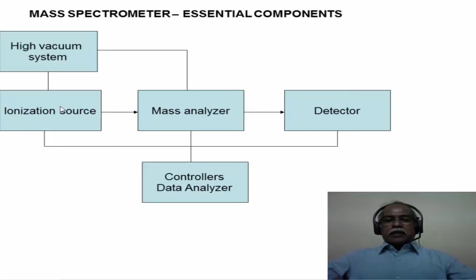Electrospray ionization mass spectrometry as an ionization source and a quadrupolar mass analyzer is a very powerful combination in mass spectrometry. Many modern spectrometers are equipped with this combination as a standard tool for mass spectrometry. Generally, in mass spectrometry we have a very high vacuum system, and the ionization source is also under high vacuum, of the order of 10 to the power minus 6 or minus 7 torr. But there is an exception in the case of electrospray ionization mass spectrometry and matrix assisted laser desorption ionization mass spectrometry, where the ionization can take place at atmospheric conditions, and then the ionized sample is taken into a vacuum chamber, into the analyzer, and so on.